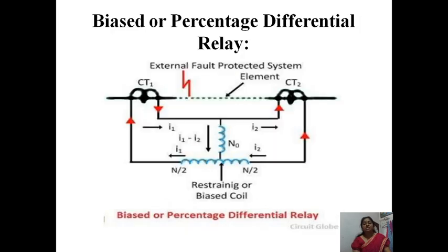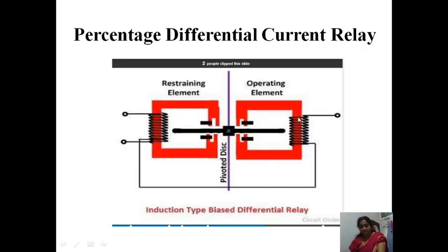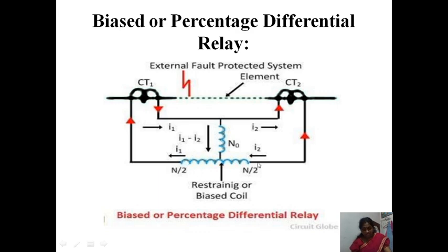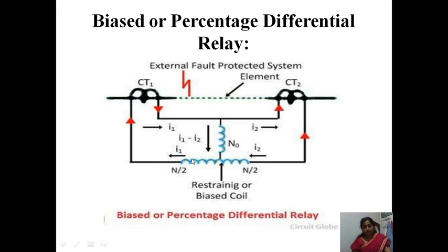This is the induction type bias differential relay. Here you can see the CTs. The operating coil has a single coil, while the restraining coil is divided into two halves — Nr/2 and Nr/2. Nr indicates the restraining coil and N0 indicates the operating coil. The current flows as I1 and I2, giving I2×(N/2) on one side and I1×(N/2) on the other, with I1 minus I2 through the operating element.